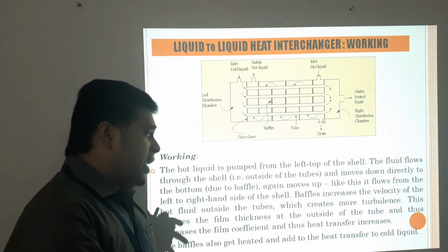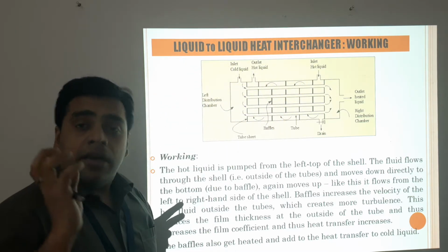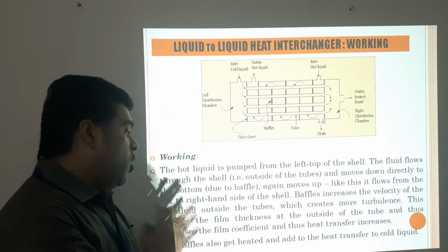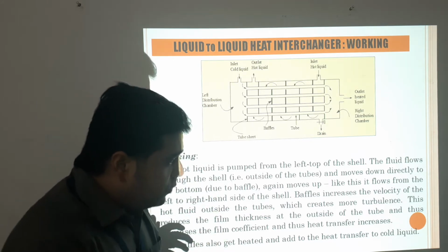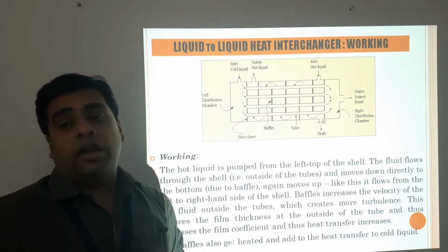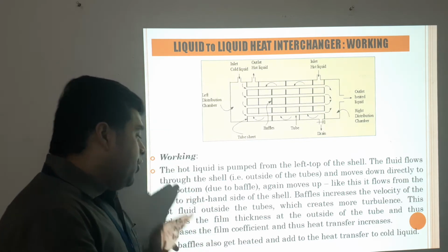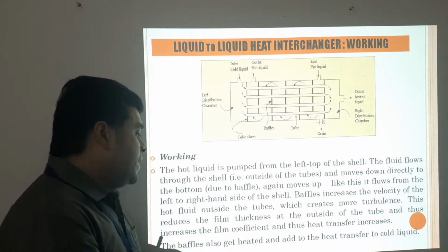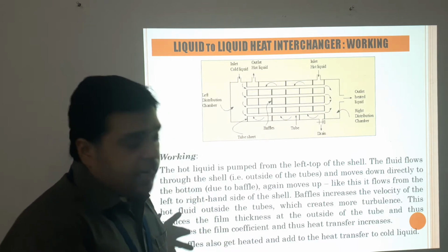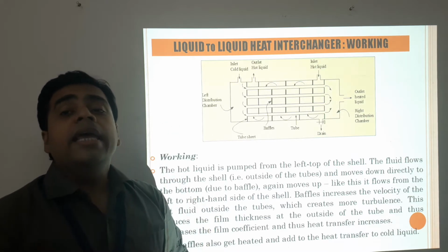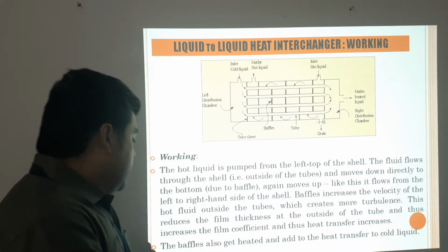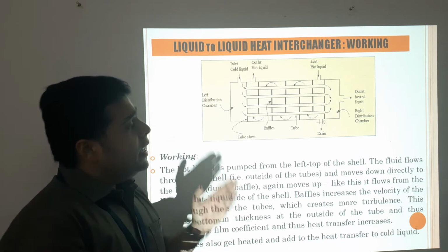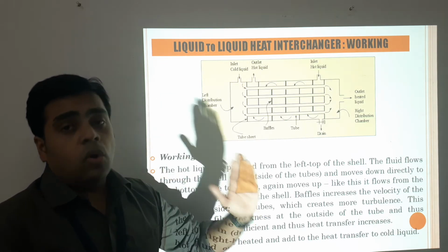Baffles are designed or kept to increase the velocity of the hot fluid outside the tubes, which creates more turbulence. This reduces the film thickness at the outside of the tube and thus increases the film coefficient and overall it improves the heat transfer. The baffles also get heated and they add to the heat transfer to the cold liquid.